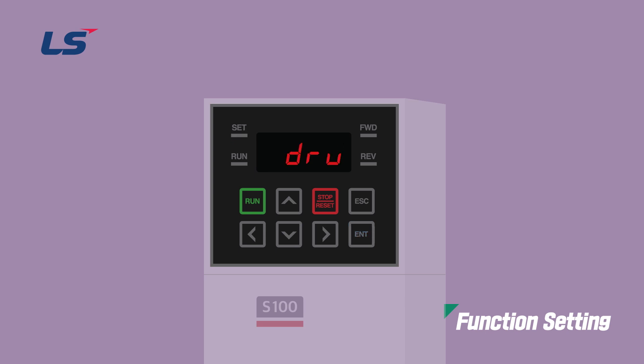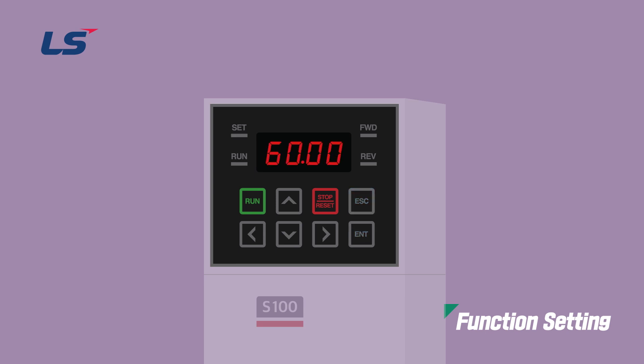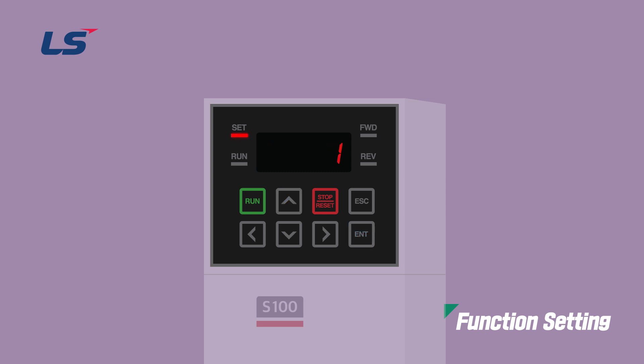The Frequency command setting method can be set in the Operation Group FRQ. In this video, we will set it to 0 keypad 1. Next, you need to set the parameters for Automatic Restart. Change PR08 to 1 YES to enable the Startup function on Reset after a trip.